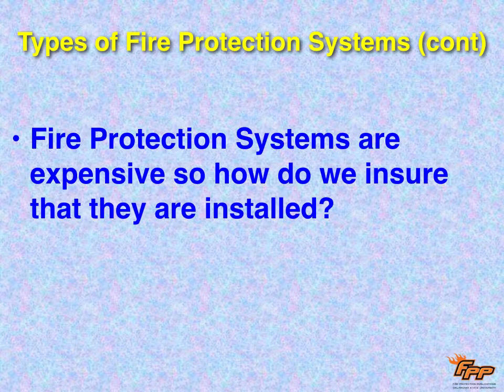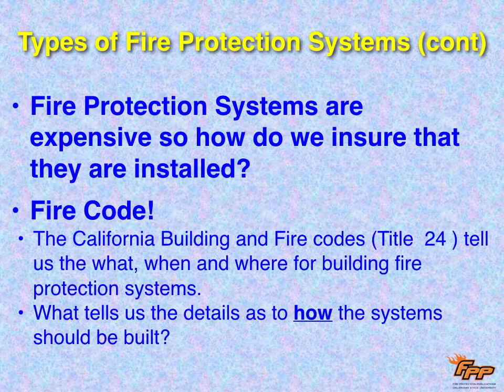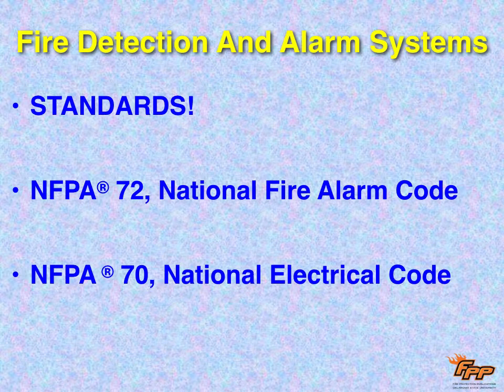Now, fire protection systems are expensive, so how are we going to ensure that they're installed? The code. We're going to make them. So, the California Building and Fire Codes, Title 24, are going to tell us the what, when, and where for the building fire protection systems. They're going to say you have to put it in these kinds of buildings or these kinds of occupancies. Now, what tells us the details as to how they should be built? Remember that? The fire code tells us what to do. The standards tell us how to do it. So if we were looking at fire alarms, we would go to NFPA 72, the National Fire Alarm Code, and we might also use the electrical code. If it was sprinklers, it would be NFPA 13. And there's a standard for almost every type of fire protection system.